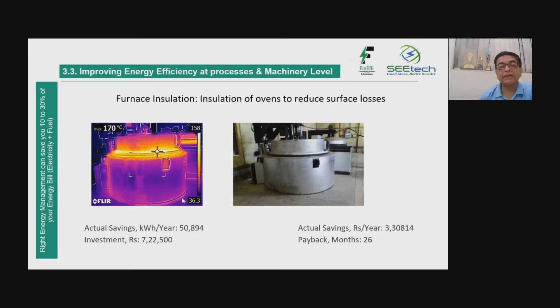Before and after, whoever is carrying out your insulation work should prove to you that the surface temperature was earlier this much and now it is this much - not just by measuring with a surface thermocouple, but by carrying out these detailed thermal scans before and after so that you get it right. Because if you don't get it right, you keep losing energy cost, and when so much temperature is there on the metallic surface, the life of your furnace or metal sheet also deteriorates. So achieving the right energy efficiency is very important, and it is very much possible.